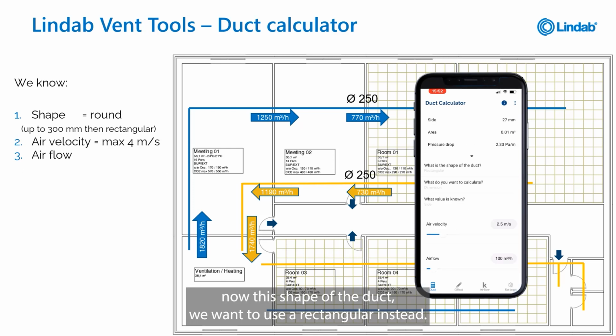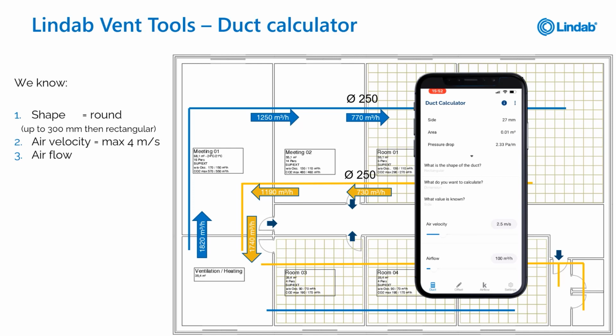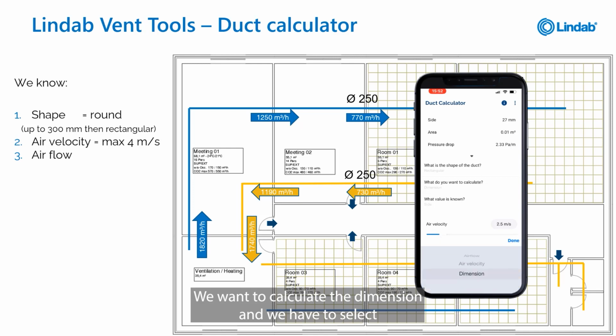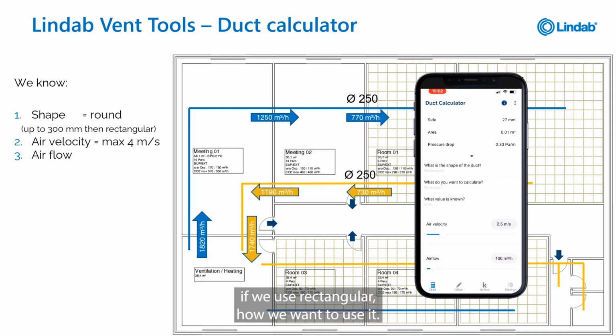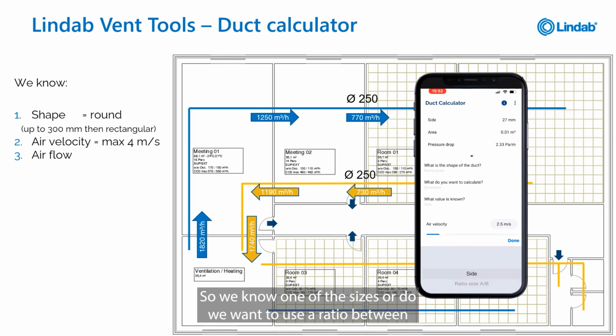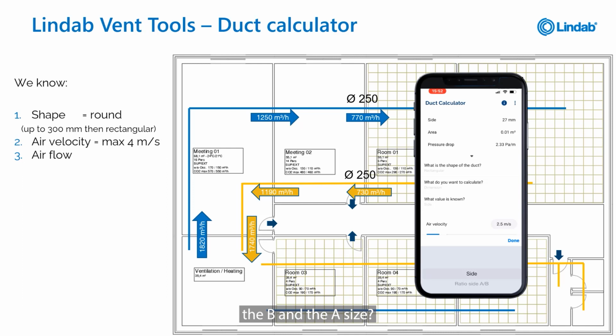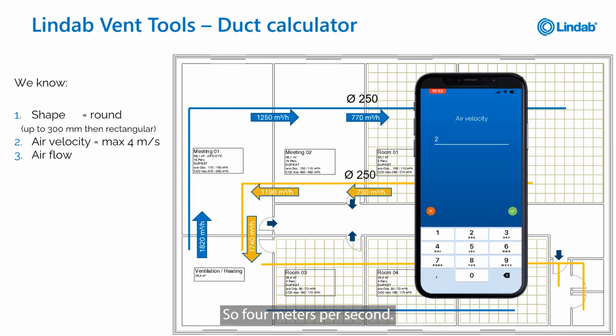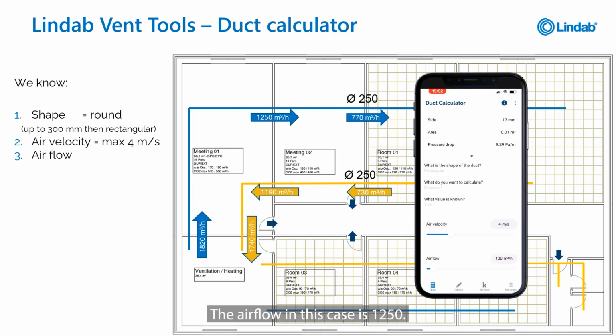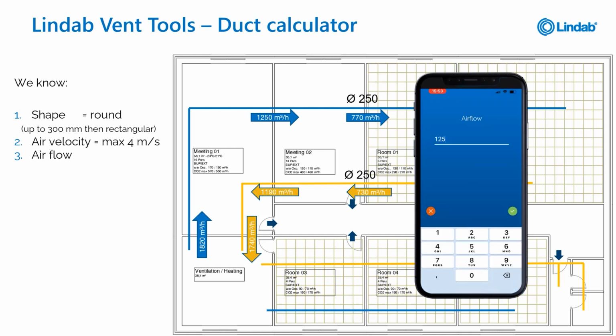We want to use a rectangular duct instead. We want to calculate the dimension, and we have to select, if we use rectangular, how we want to use it. So we know one of the sizes, or do we want to use a ratio between the B and the A size? The air velocity should be the same, so 4 meters per second. The airflow in this case is 1250.